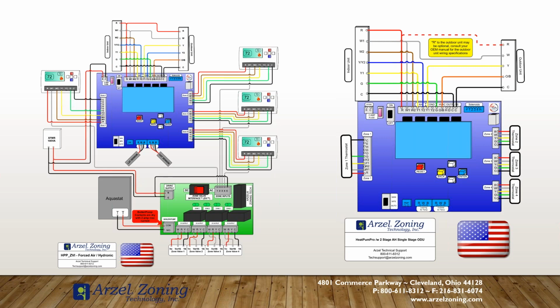So if I have a customer, they want warm floors. With the Arzel system, there are no master thermostats. All thermostats are master. So with the Heat Pump Pro, you can set a zone weight priority. So if you do have one zone that may at times have dissimilar calls to the other zones, you can set the zone weight priority and make that zone a larger weight. However, our panels don't have a master thermostat as far as operation goes.